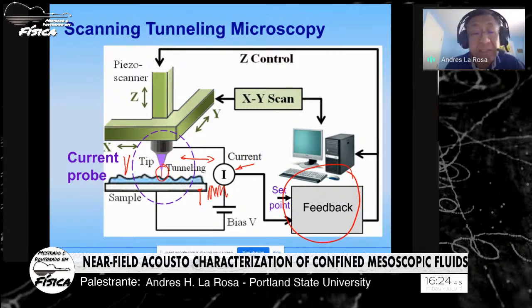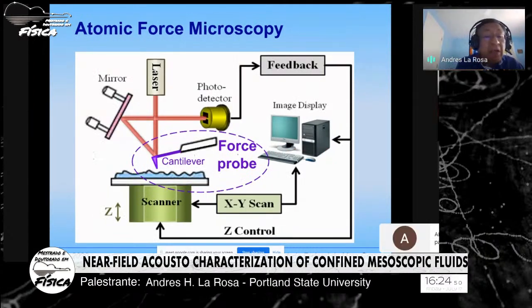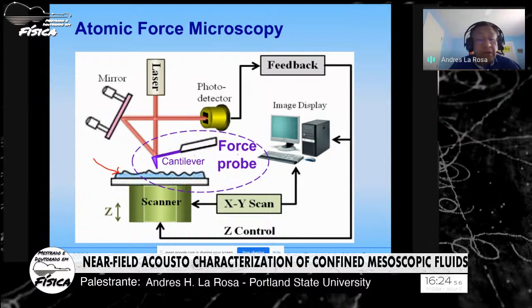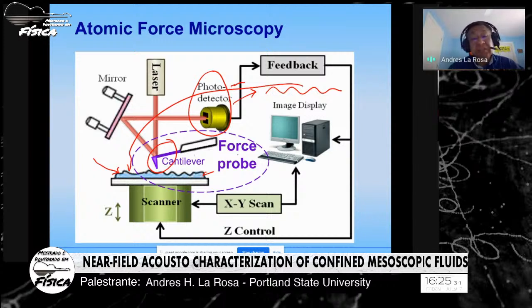So soon after came atomic force microscopy. Now your sample could be conductive, could be an insulator, it doesn't matter. Why? Because now your probe is not an electrical current probe, it is a force probe. It measures the deflection of the cantilever. When the cantilever is scanned laterally, due to the interaction with the surface it goes up and down, so that your detector registers up and down. With these signals you create the topography, a replica of your surface. So this is the atomic force microscope.